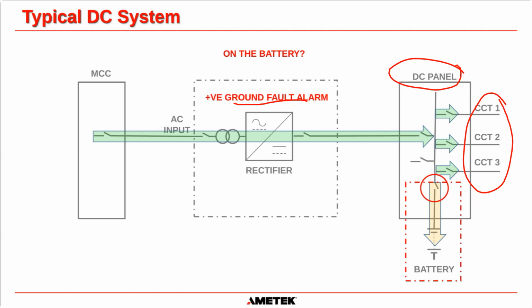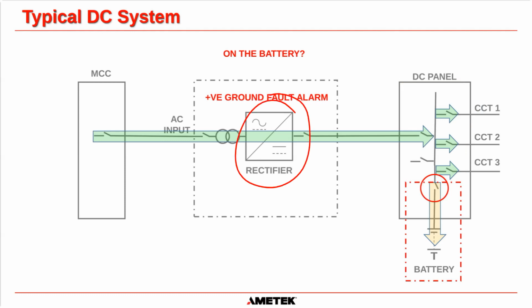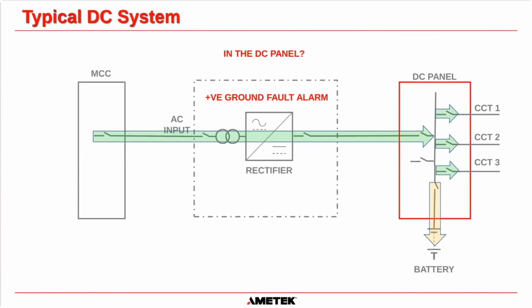So you have to do this methodically. It's like a criminal investigation. You've got to do it methodically. So you're working out, okay, I'll start here and let's move along the line until we find out where it is, okay? So we've ruled out it's not on the charger. It's not on the cable between the charger and the DC panel, and it's not on the battery, okay? The next point we're going to look at is, is it in the DC panel?